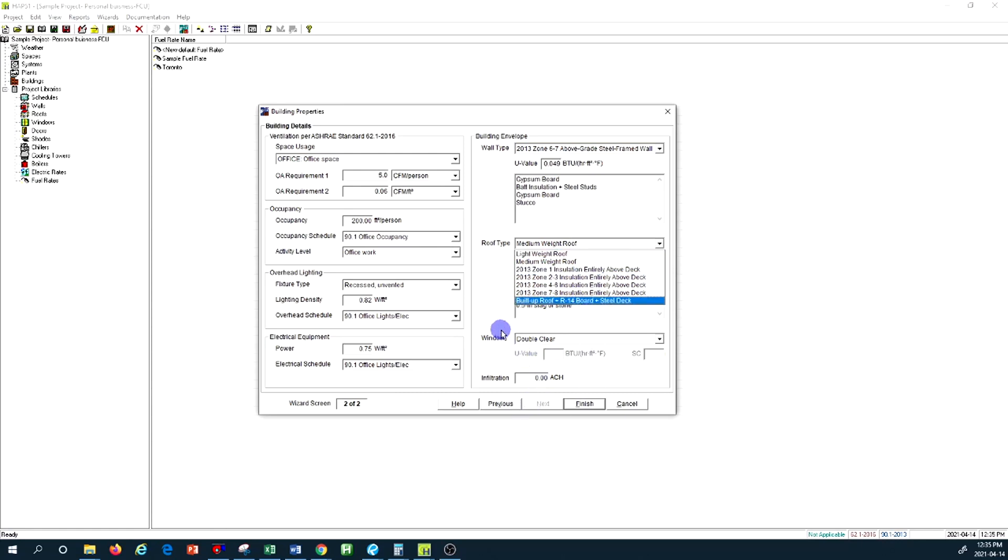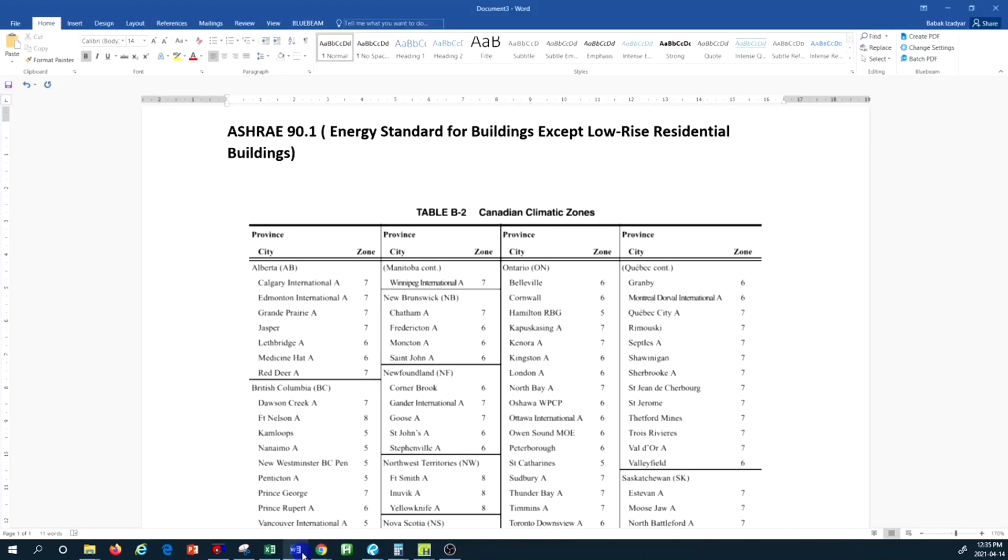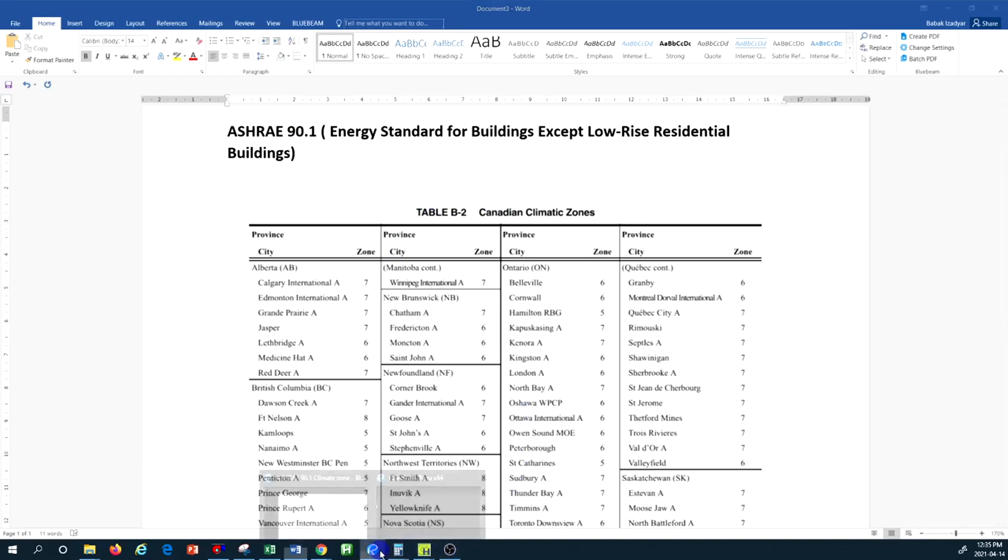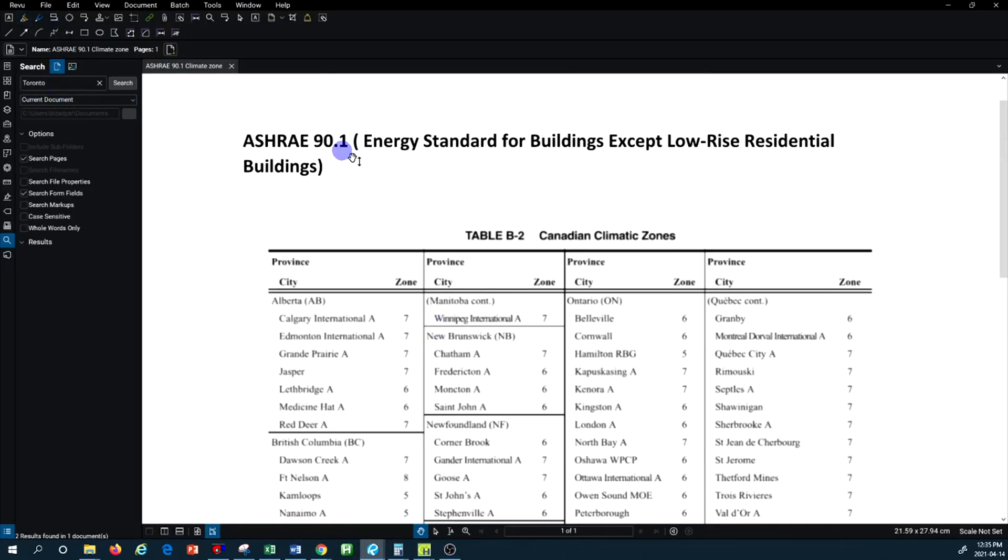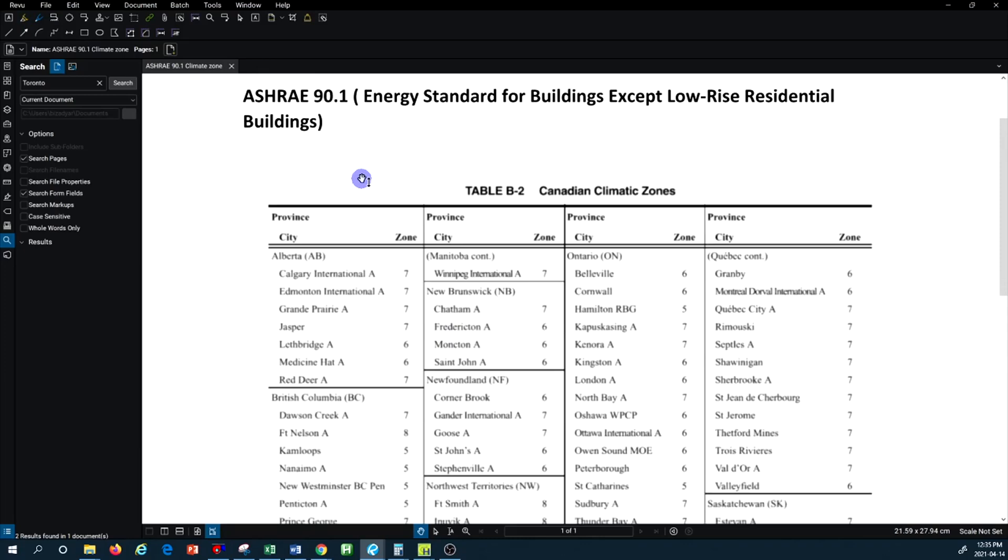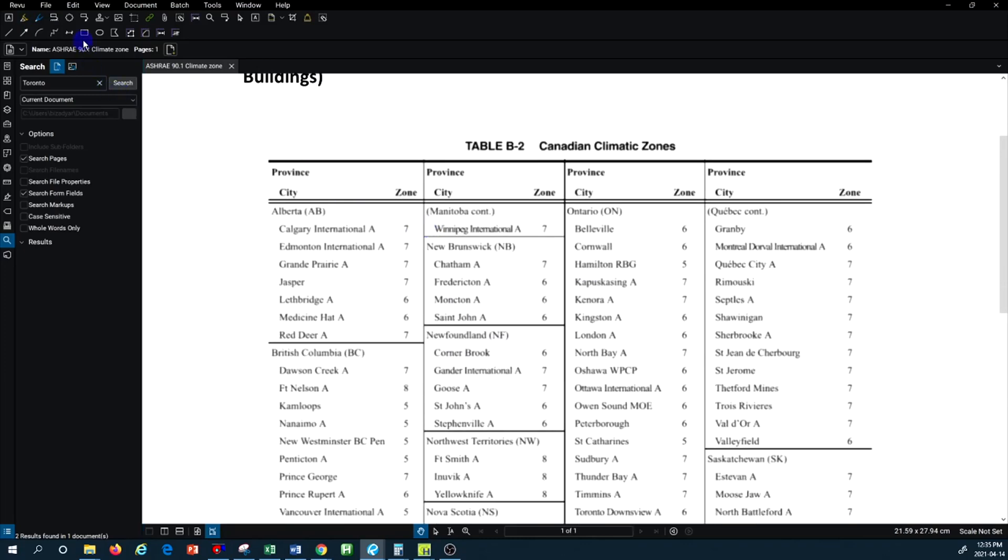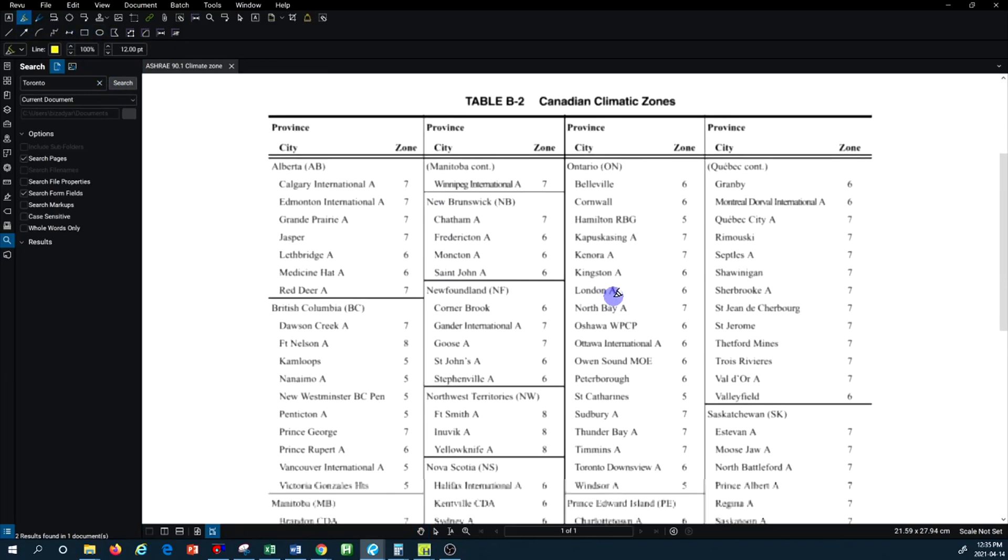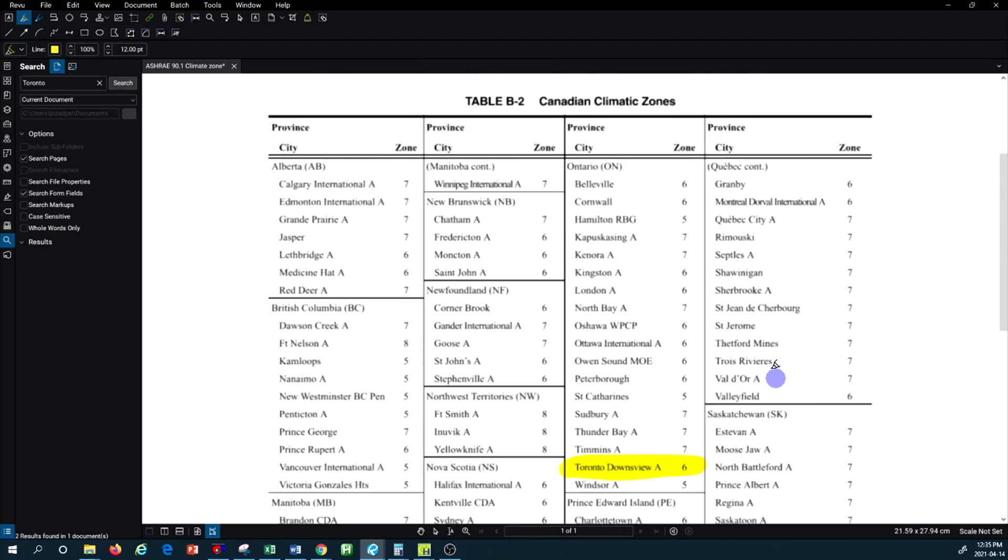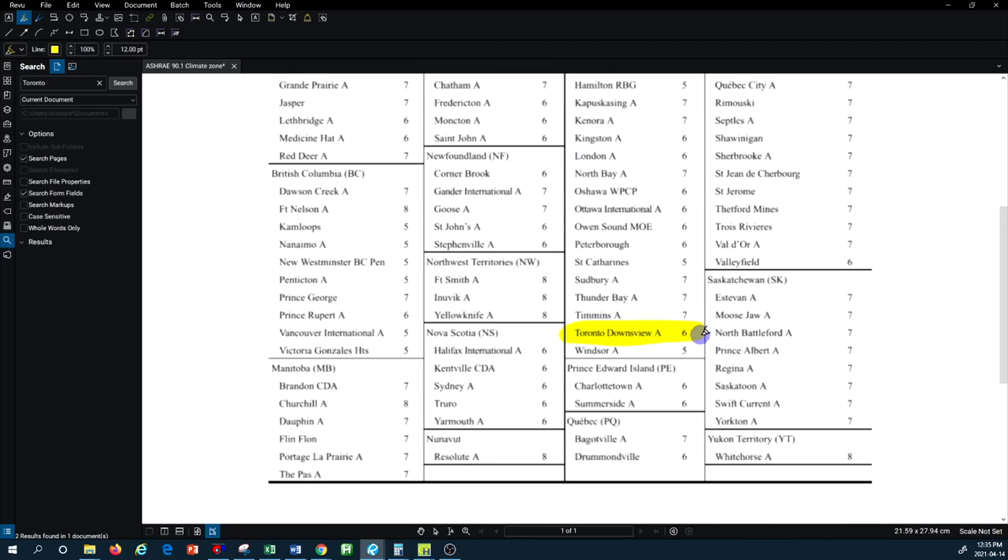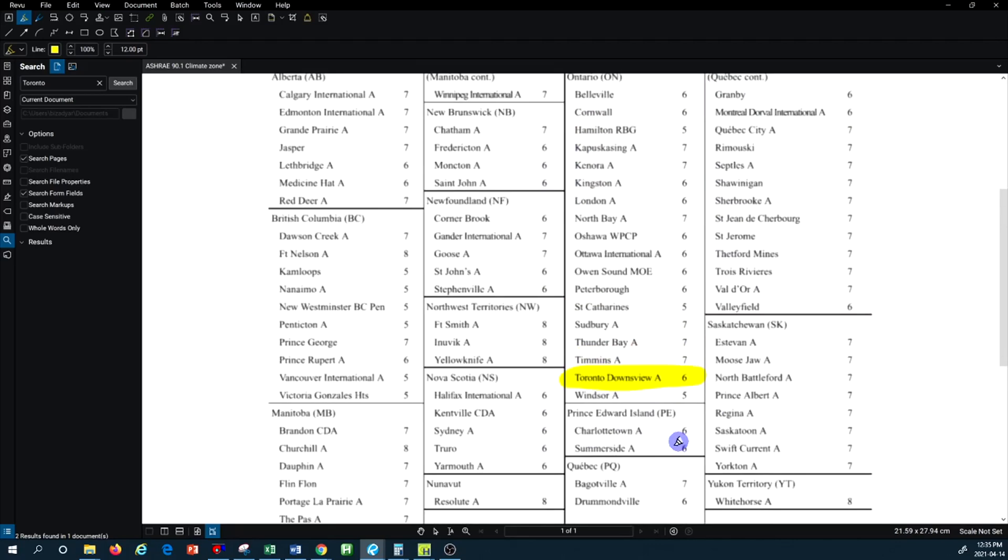ASHRAE 90.1 for energy, I can show you a table here. This table is from ASHRAE 90.1 energy standard for building except low-rise residential buildings. I'm going to show you what I mean by that. So if you go to the latest ASHRAE standard, you can find the zone based on your geographic location. I'm in Toronto so I'm coming to here and basically that's the zone I'm located in.